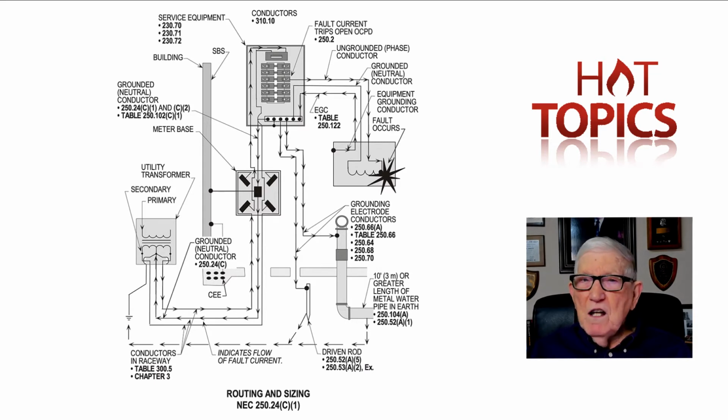I was really lucky. It only damaged the neutral bar, and it had been a federal type panel. I didn't damage any of the ungrounded bus bars or the conductors there. Just that neutral, I'd kind of whipped up on it. And we just had them change it out and put in a larger one. But I goofed up there because I didn't take 2 steps.